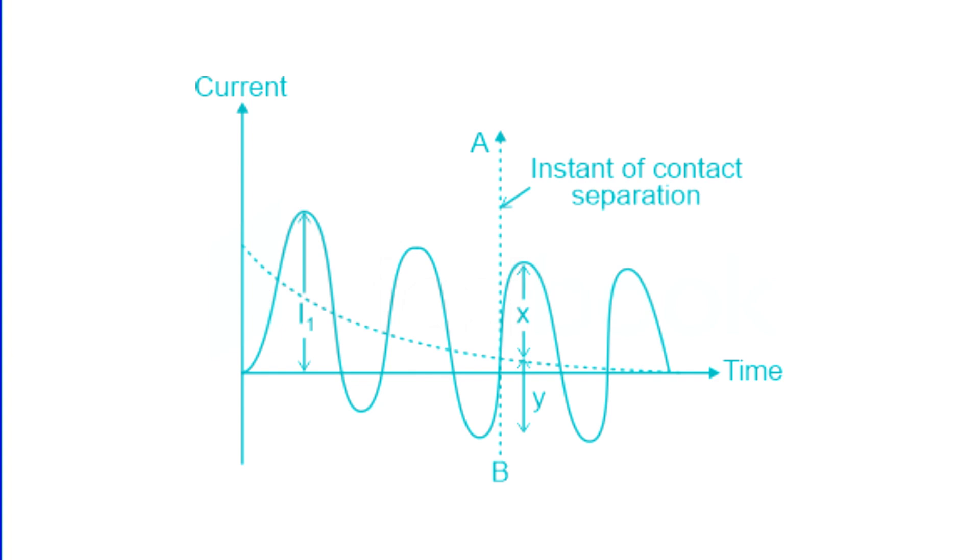From the previous discussion, it is evident that the making current is the peak value of current during the sub-transient state including the DC offset value. In contrast, the breaking current is the RMS value of the current at the moment the breaker contacts separate.